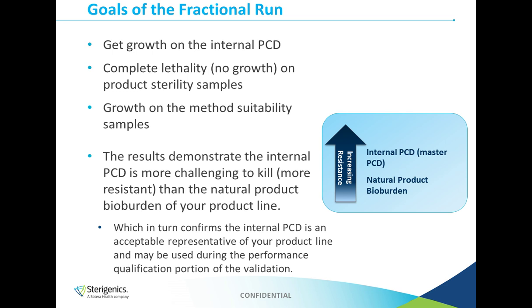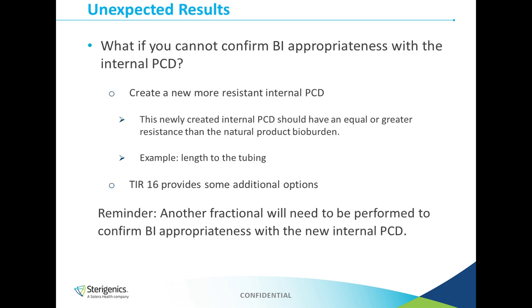sterility samples. Now the results from this would demonstrate that that internal PCD is more challenging to kill than the natural product bioburden. And ultimately, it confirms that that internal PCD is an acceptable representative of your product line. Remember, you're using this internal PCD for your validation, so you want it to be representative of the actual products that are going to be sterilized. And then this internal PCD would be used for your performance qualification portion of the validation, which would be your half cycles and your full cycles.